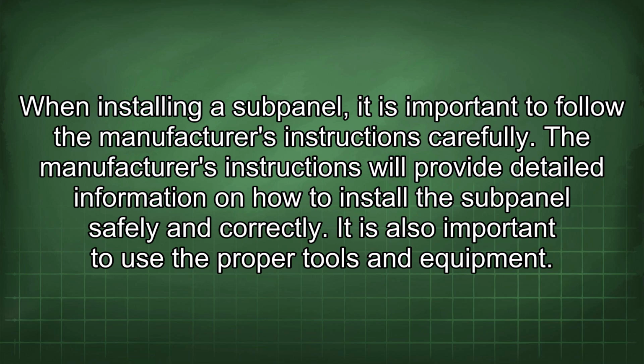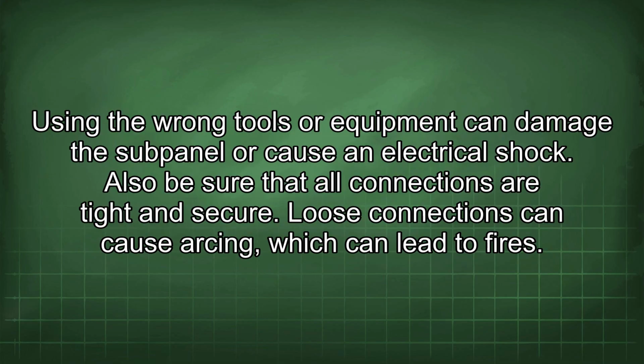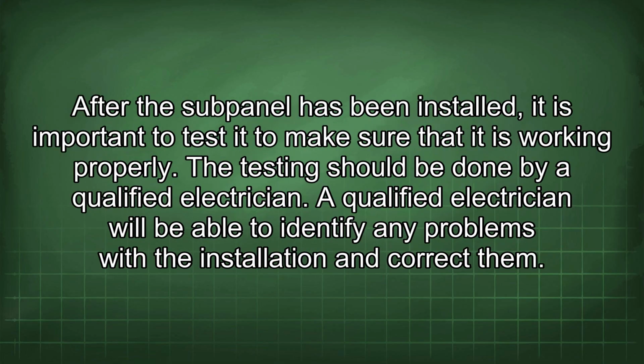It is also important to use the proper tools and equipment. Using the wrong tools or equipment can damage the subpanel or cause an electrical shock. Also be sure that all connections are tight and secure. Loose connections can cause arcing, which can lead to fires. After the subpanel has been installed, it is important to test it to make sure that it is working properly. The testing should be done by a qualified electrician. A qualified electrician will be able to identify any problems with the installation and correct them.